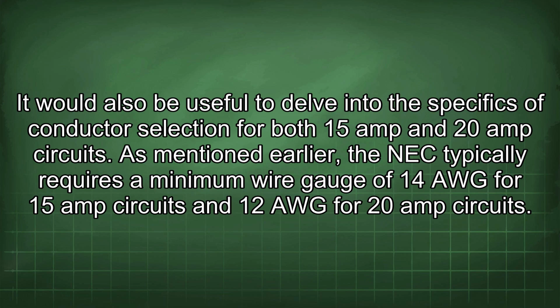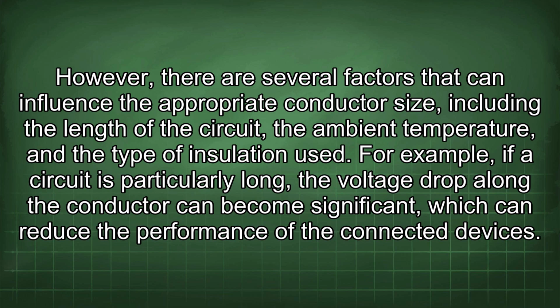As mentioned earlier, the NEC typically requires a minimum wire gauge of 14 AWG for 15 amp circuits and 12 AWG for 20 amp circuits. However, there are several factors that can influence the appropriate conductor size, including the length of the circuit, the ambient temperature, and the type of insulation used.